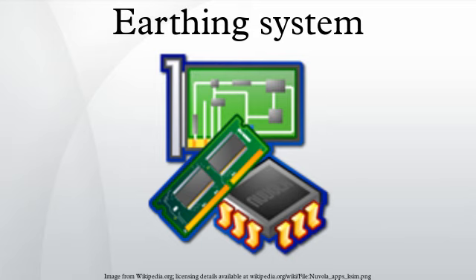In remote areas, where the cost of an additional PE conductor outweighs the cost of a local earth connection, TT networks are commonly used in some countries, especially in older properties or in rural areas, where safety might otherwise be threatened by the fracture of an overhead PE conductor by, say, a fallen tree branch. TT supplies to individual properties are also seen in mostly TNCS systems where an individual property is considered unsuitable for TNCS supply. In Australia, New Zealand and Israel the TNCS system is in use.